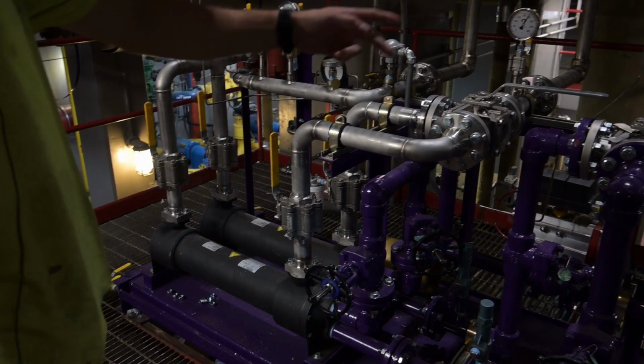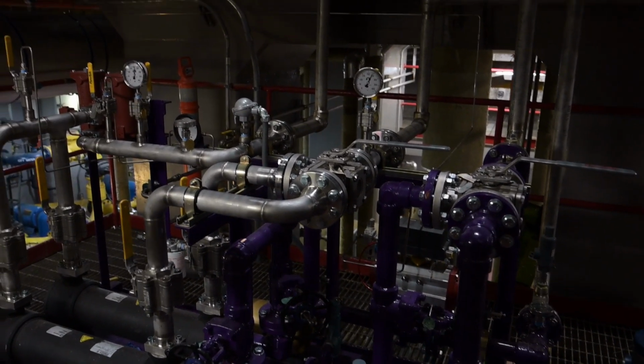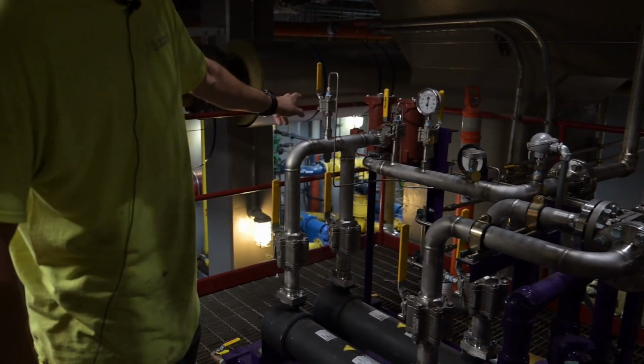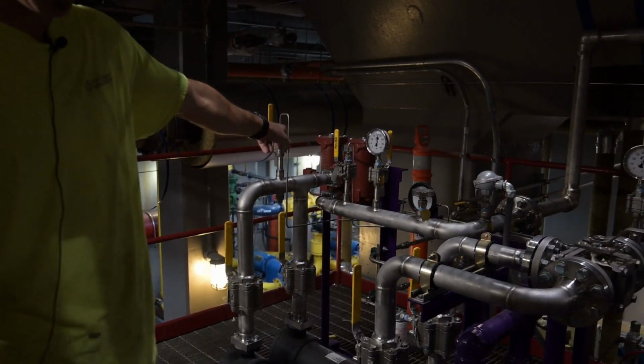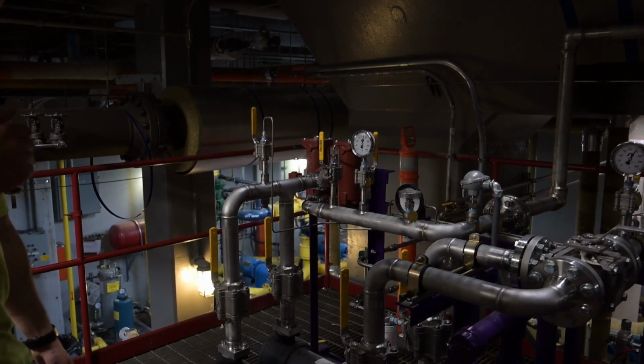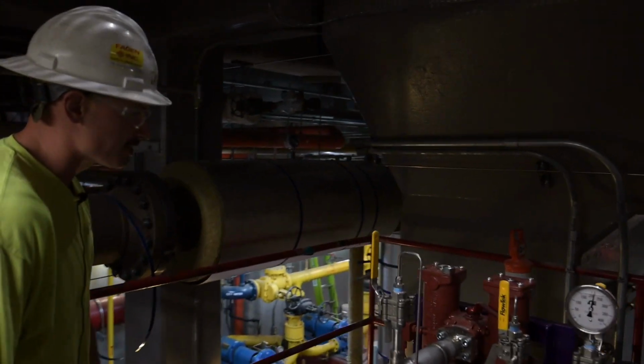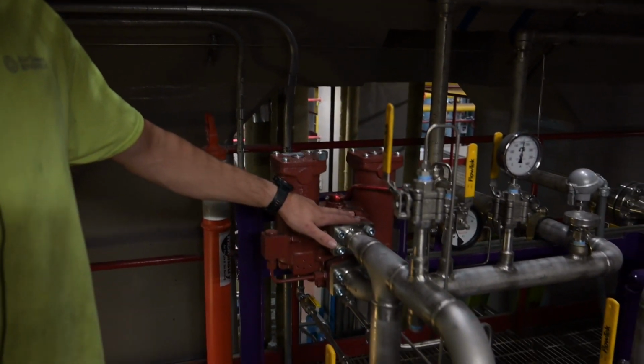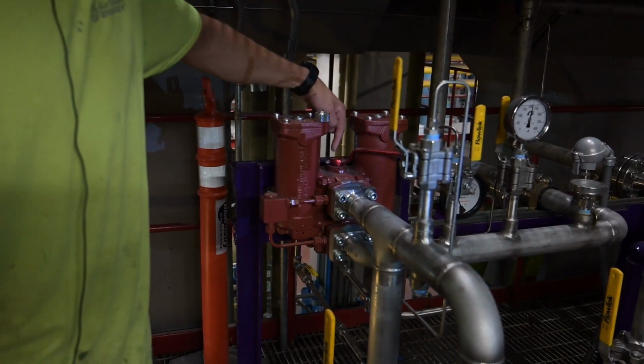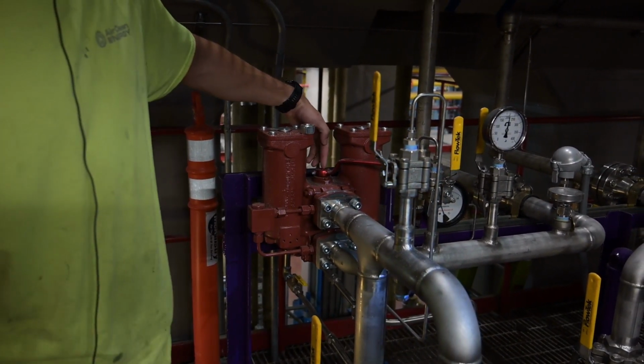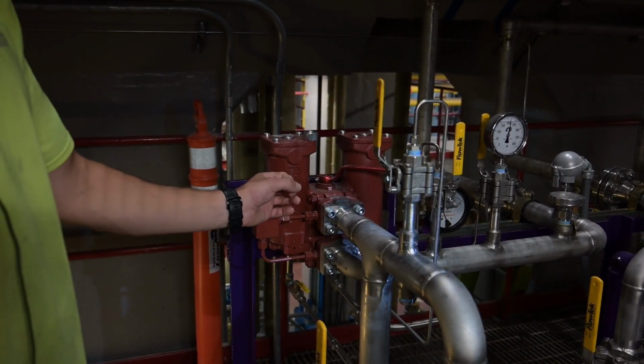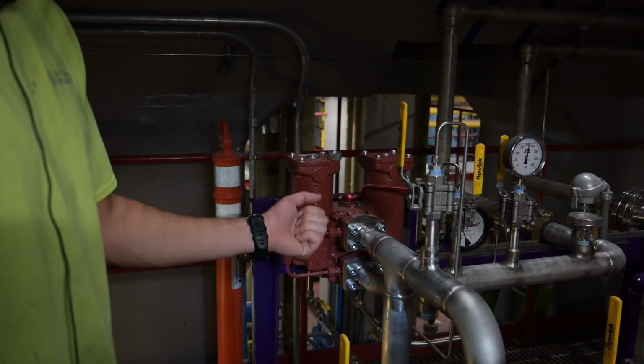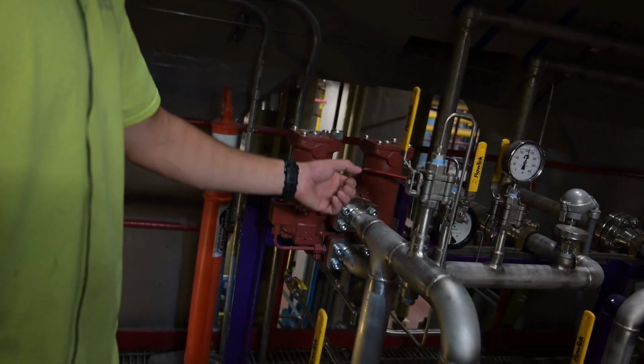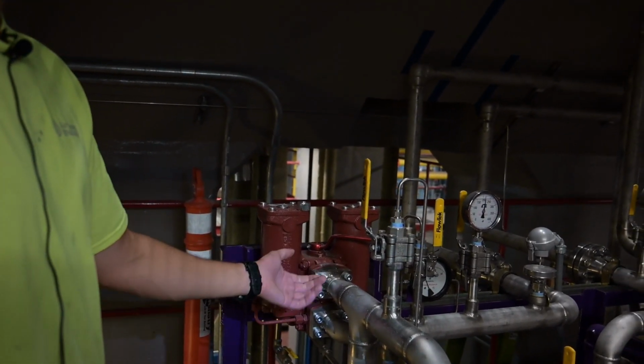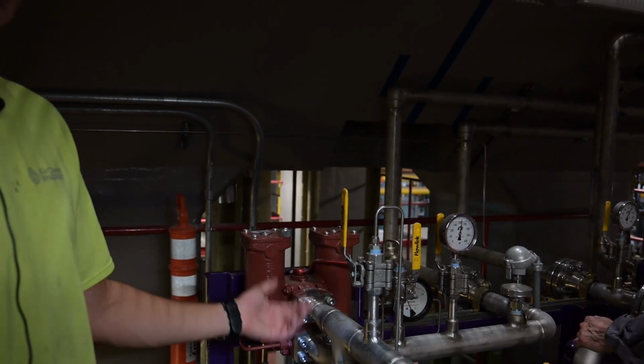But oil comes into the skid, through the heat exchanger, up into the filter housing. It's a duplex filter housing. Come over here and talk about how to change it. It's got a little indicator up here that corresponds to markings on the square plug that the handle is mounted to. And that's going to indicate which filter is in service. You can change the non-in-service filter while the other is in service.